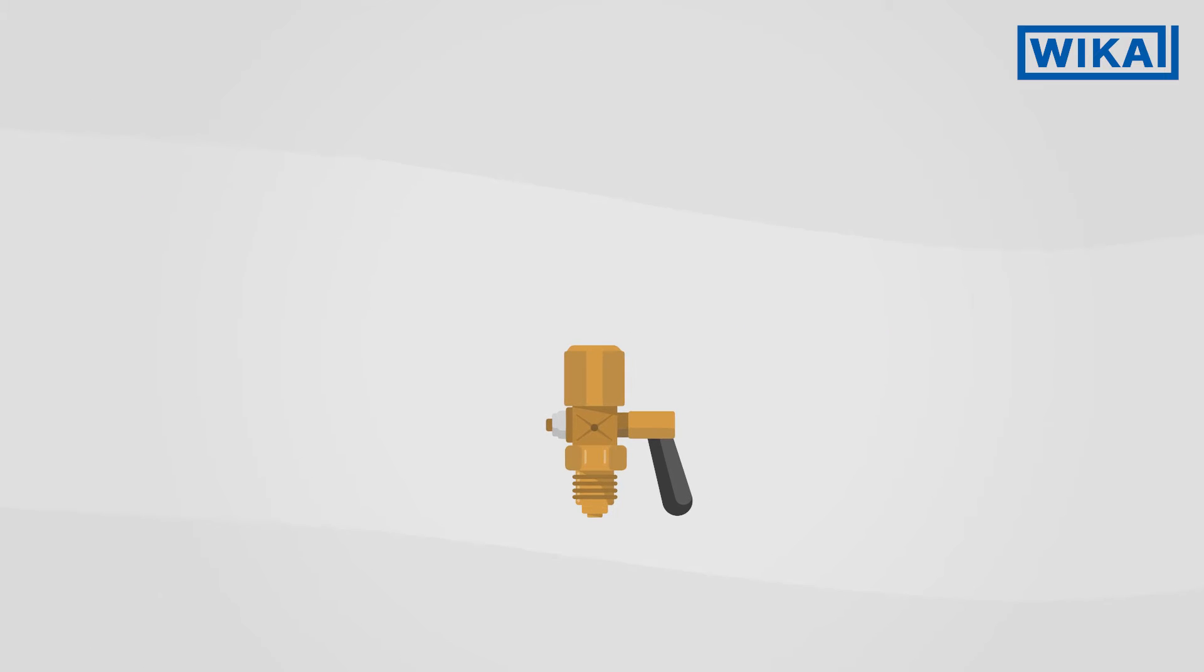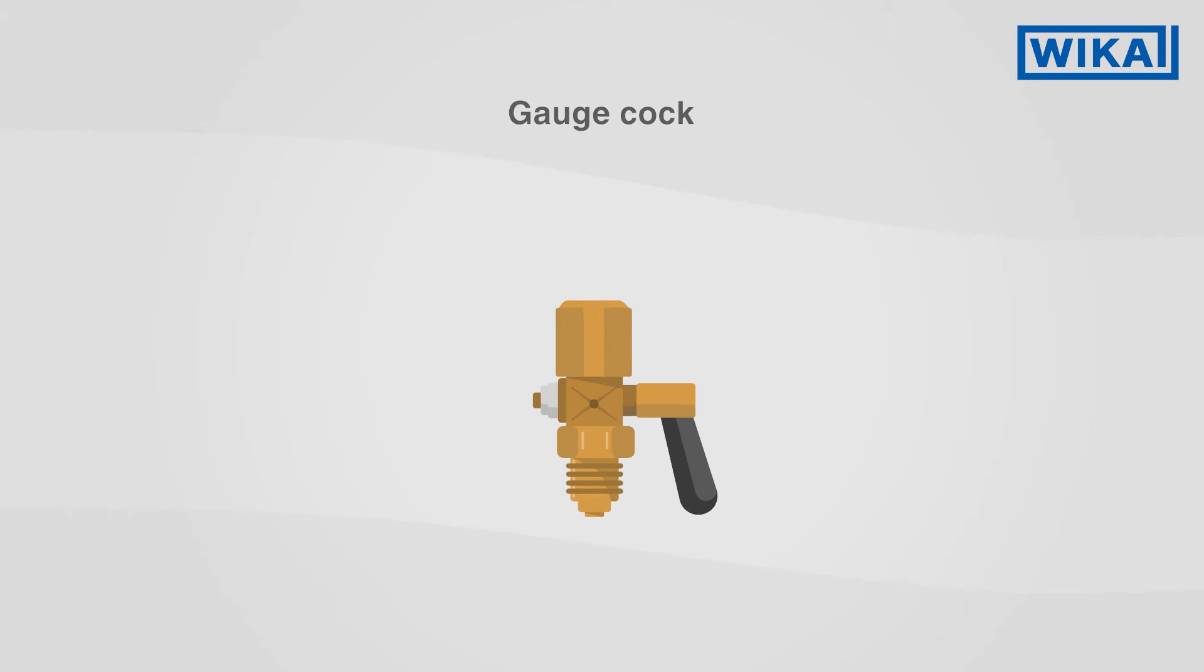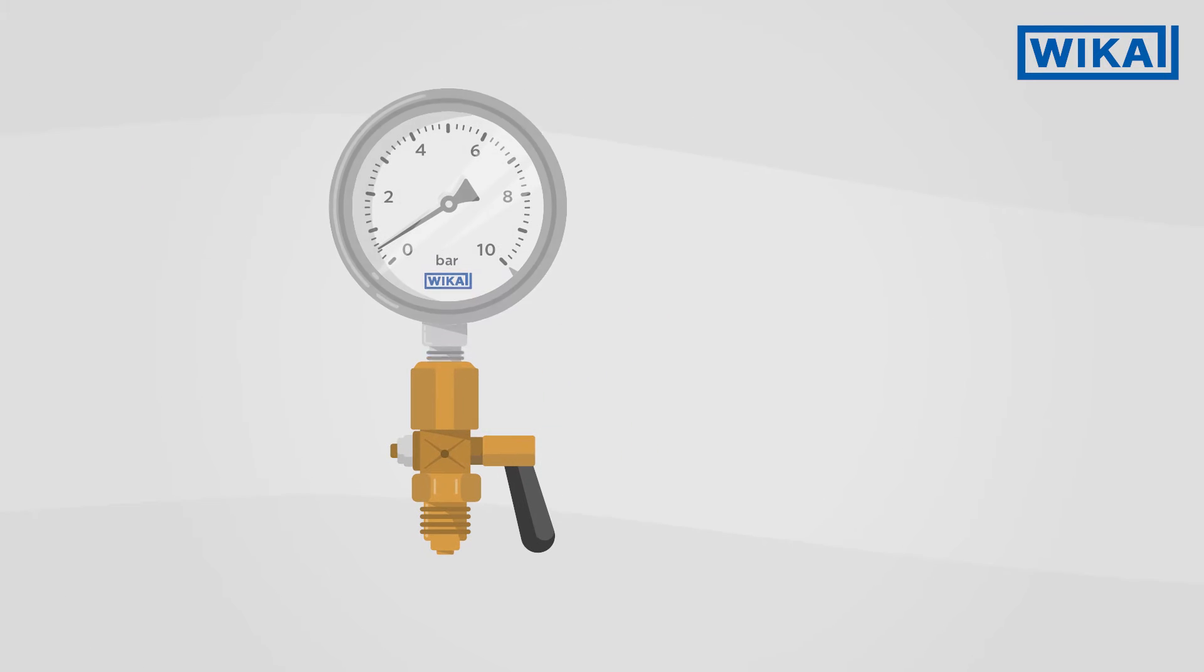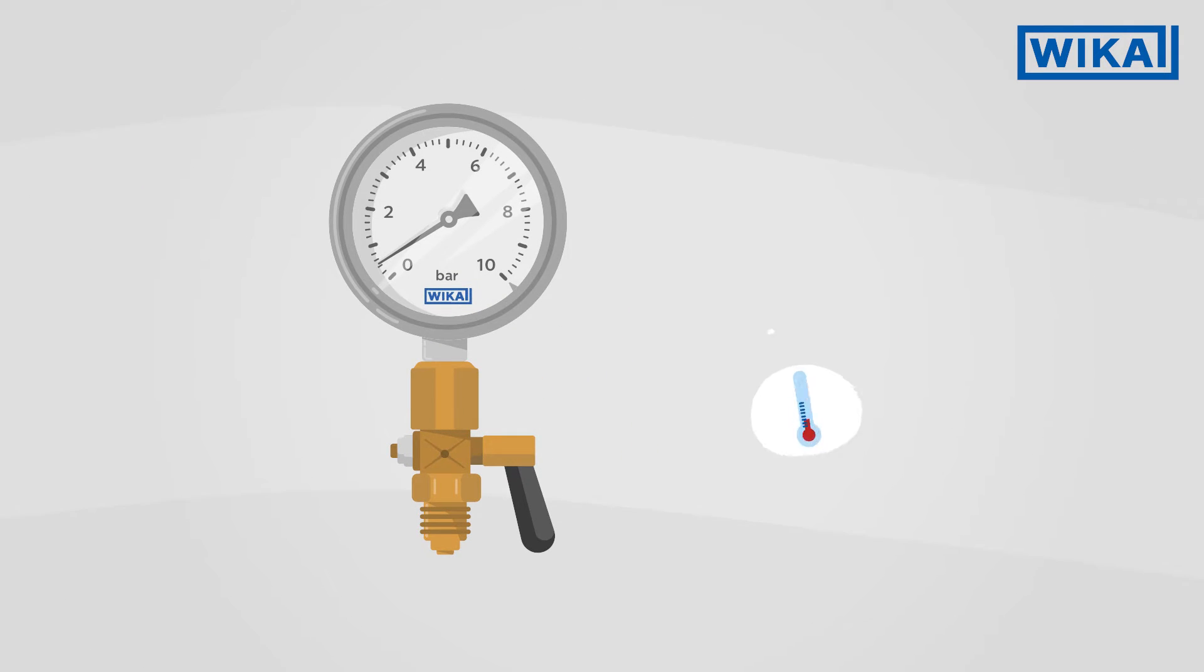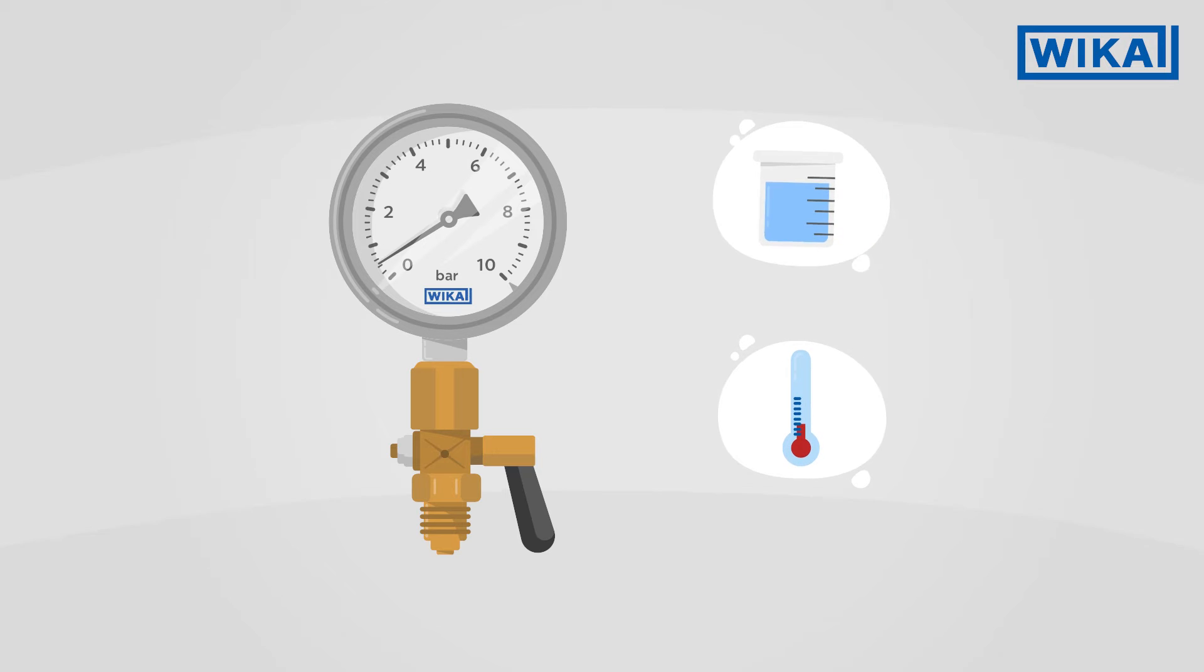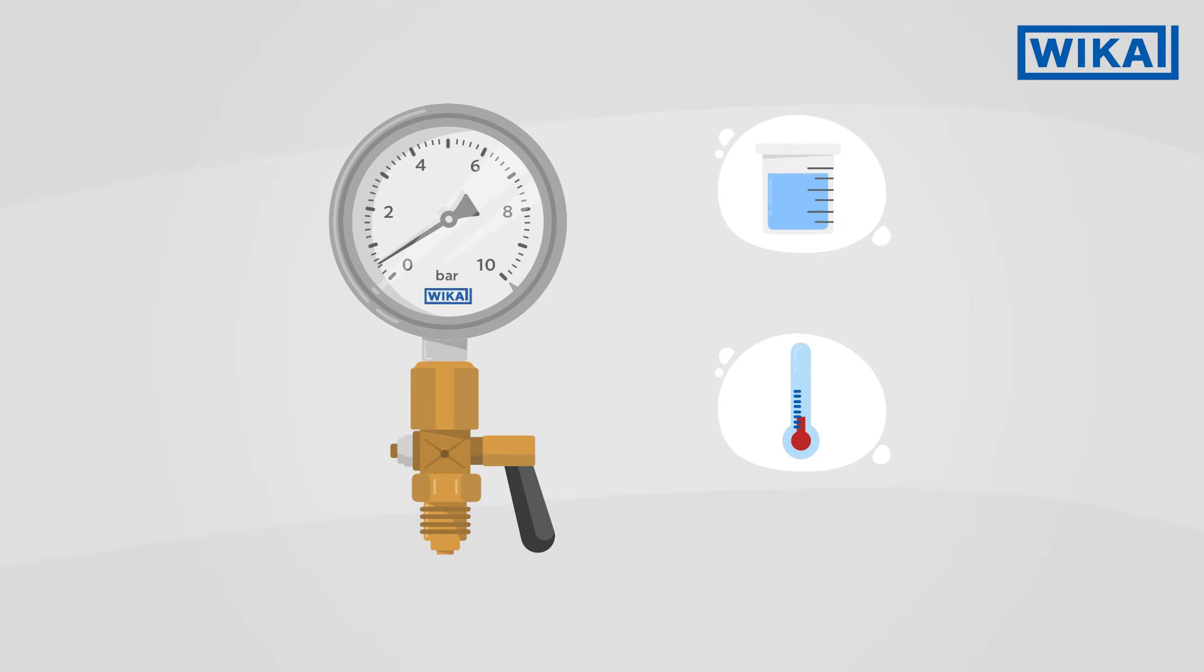The simplest type is the gauge cock. If the process pressure and process temperature are low and a non-critical medium is being used, a gauge cock is sufficient.